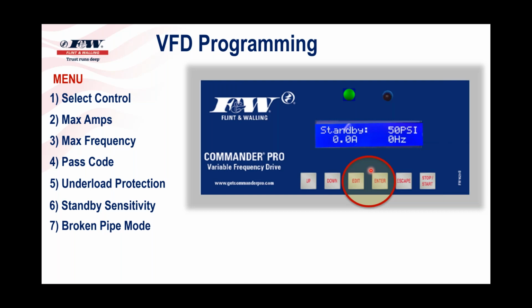This broken pipe mode is nothing more than a timer, and you can set it from 4 hours, 8 hours, 24 hours. What happened is the pump never built up pressure, never shut off, and the drive did what it was supposed to do. It said, dude, you've been running, you've not built up pressure, you've not shut off, there must be a leak somewhere. Boom, it kicked out on broken pipe mode. And the drive did exactly what it was supposed to do.